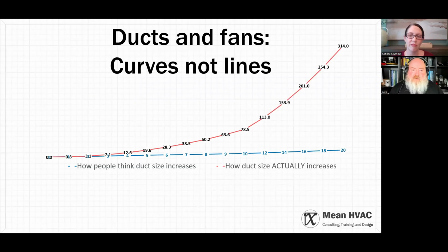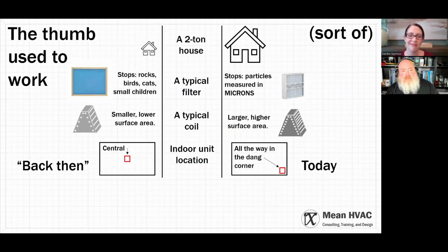That used to work once upon a time because a 2-ton house used to be a tiny little thing. They didn't even sell 2-ton units in Texas, it was a special order, because we didn't insulate our houses and needed bigger air conditioners. Now you can get a 1,500 square foot house that needs a 2-ton system very easily. A code minimum new house, that's going to be the case.